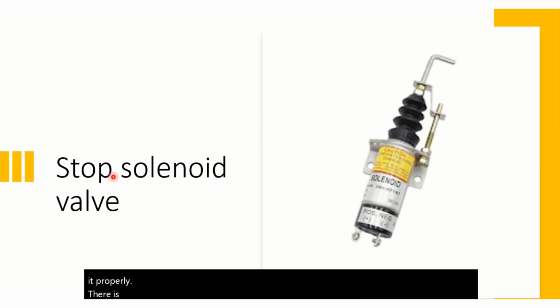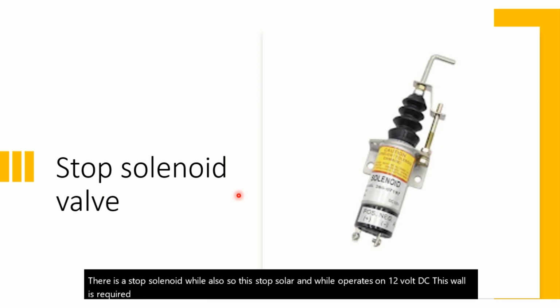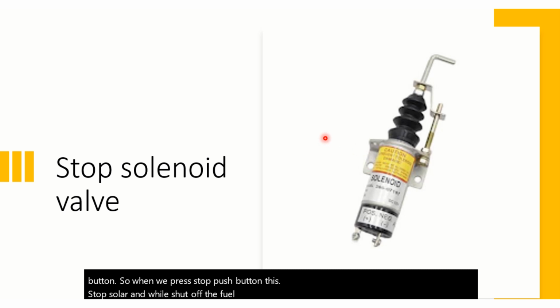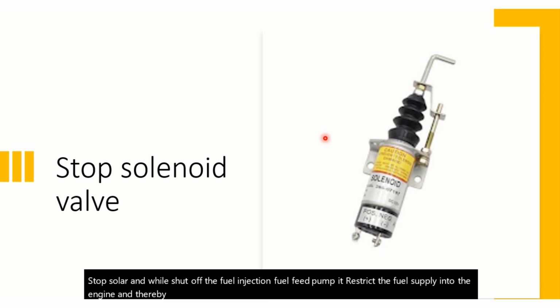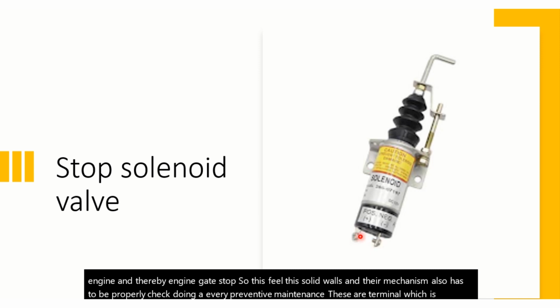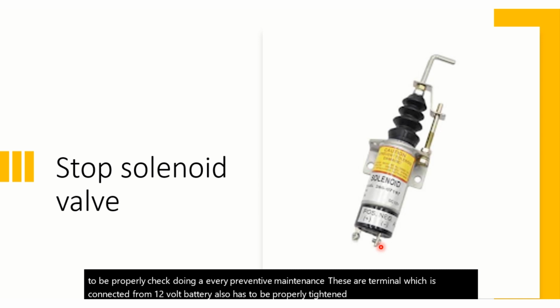There is a stop solenoid valve also. This stop solenoid valve operates on 12 volt DC. This valve is required to shut down or switch off the engine when we press the stop push button. When we press the stop push button, the stop solenoid valve shuts off the fuel injection fuel feed pump and restricts the fuel supply into the engine, and thereby the engine stops. So these solenoid valves and their mechanism also have to be properly checked during every preventive maintenance. The terminal connected from the 12 volt battery also has to be properly tightened, and it should be free from any rusting.